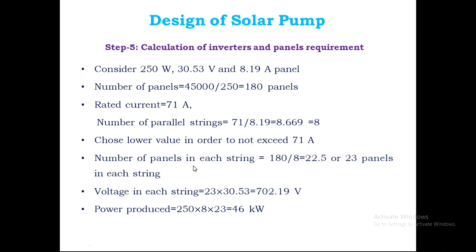And in each string, how many panels are required? How can you calculate? 180 by 8. 8 number of strings. So in each string, 23 panels are required. Right. Now you can verify.